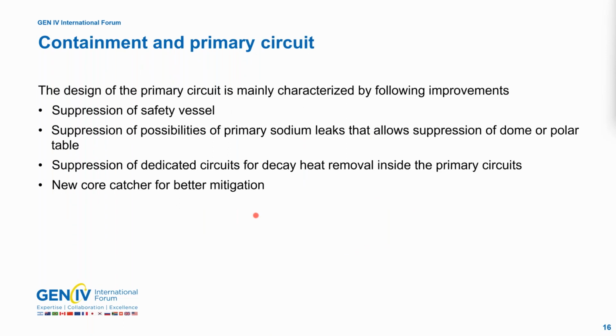Now, after the core of the reactor, we arrive at the containment and the primary circuit. The design of the primary circuit is mainly characterized by the following improvements. We suppressed the safety vessel. We suppressed the possibility of primary sodium leaks, which allows the suppression of the dome or the polar table. The dome was on the Superphénix reactor, and the polar table was on the ASTRID project. And so in ESFR-SMART, we try to suppress this very expensive feature.